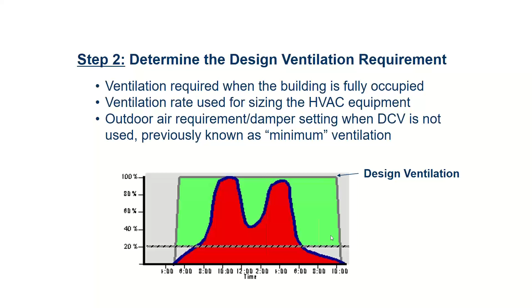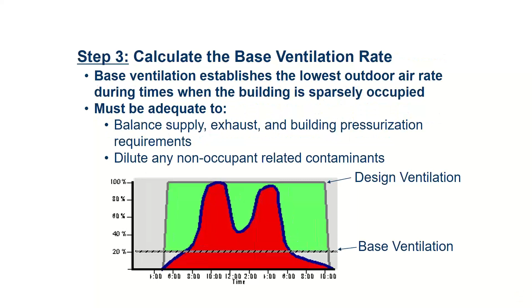I'm going to intentionally open up my outside damper to get free cooling, which means I don't have to run my compressor, which is the most expensive single item I have to run. So yes, during economizer hours, you get a huge amount of savings, but it does not come from the demand ventilation. It comes from the free cooling. All right, we keep moving on this chart here because we've got a whole bunch of stuff to go through still.